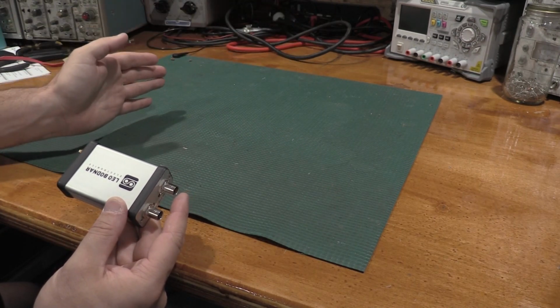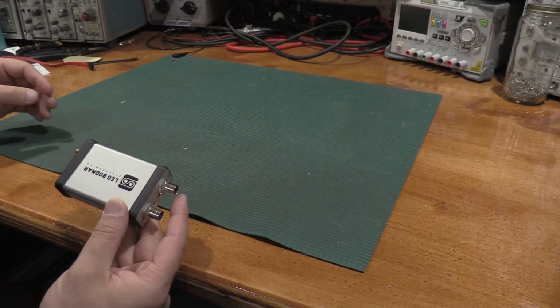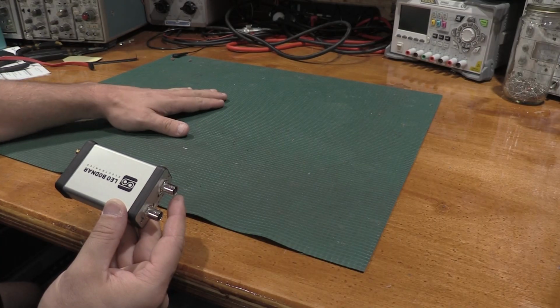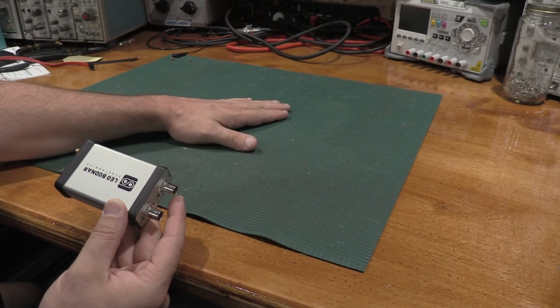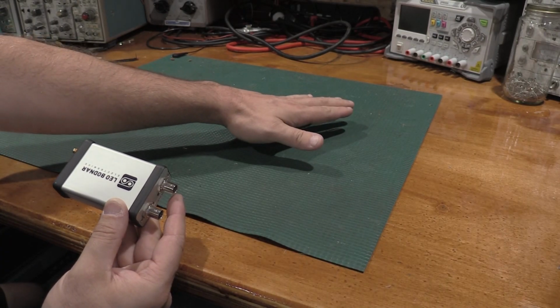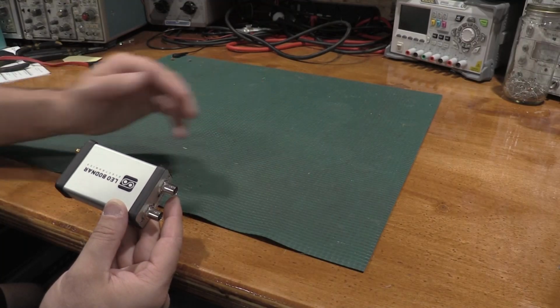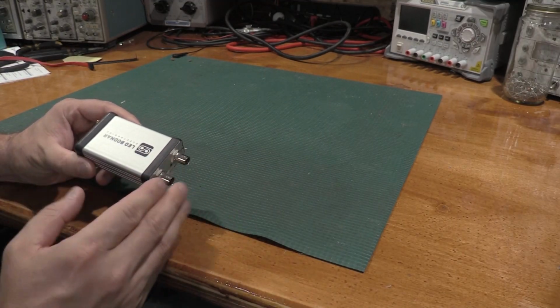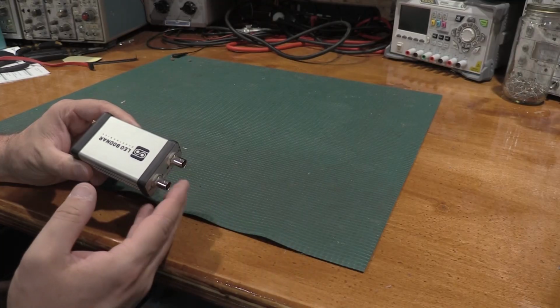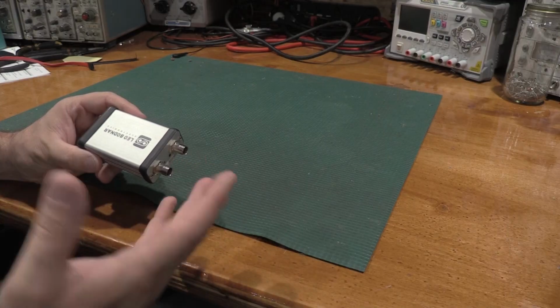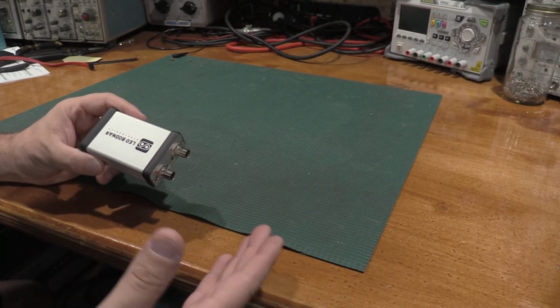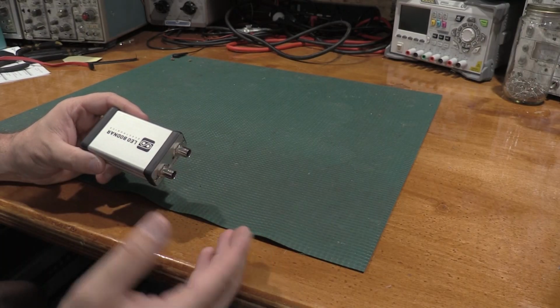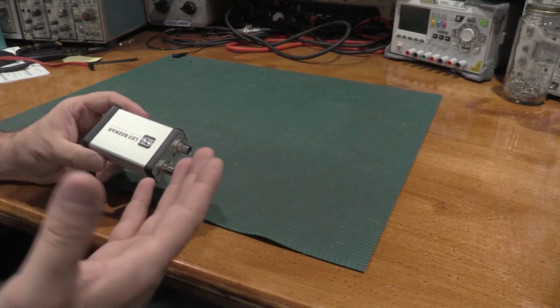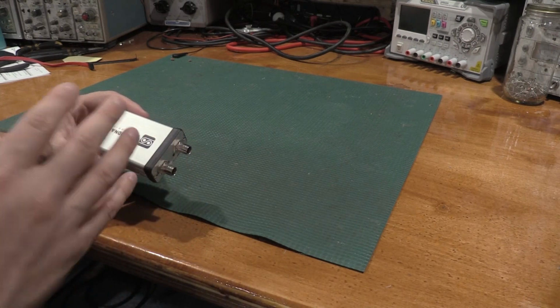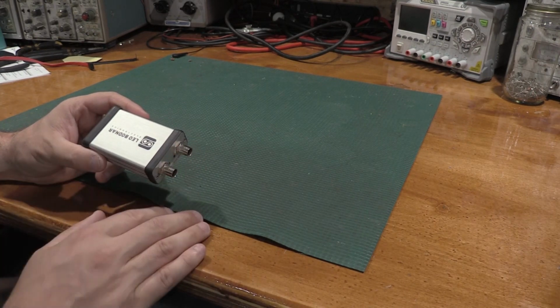So the stabilization chain is that the GPS signal disciplines the rubidium for long-term stability, but the rubidium disciplines the output for short-term stability. Short-term, these GPSDOs wander a little bit. It's not a lot, but it is a little bit. You get, I believe, 2 or 3 decimal places more accuracy on a rubidium standard, and that's about where the cost benefit ratio kind of falls off.